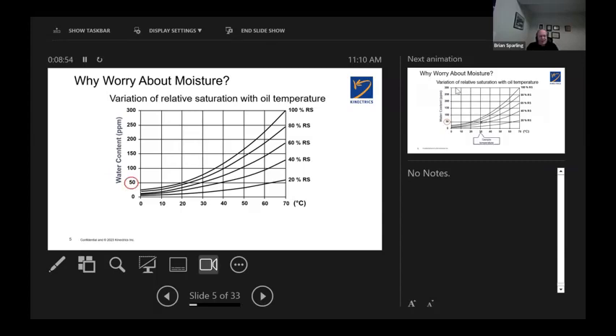You send a sample to the laboratory, and they've measured and come back to you and say, okay, there's 50 parts per million of water in this sample. Fortunately, the fellow taking the sample at the time has recorded the temperature of the sample, 30 degrees C. You can plot it on this saturation curve, and that's what this is. It's the moisture in oil saturation curves at different levels of moisture saturation of the oil. This blue dot falls on the line of 60% saturation. This is not good. It means its dielectric capacity has been reduced by more than 50%, and I guarantee you that transformer is wet.